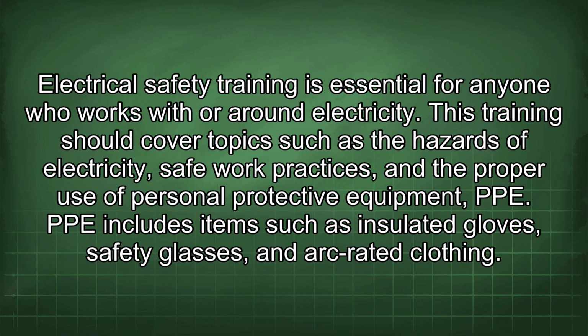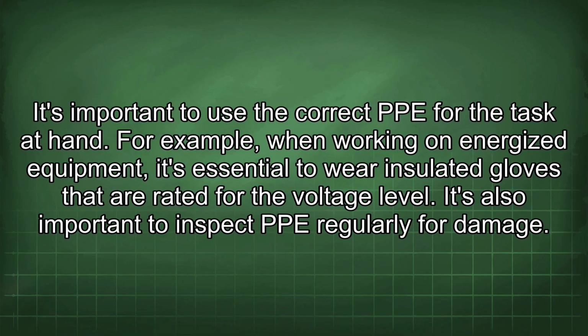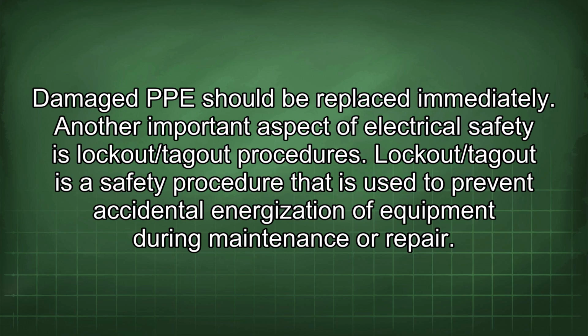This training should cover topics such as the hazards of electricity, safe work practices, and the proper use of personal protective equipment, PPE. PPE includes items such as insulated gloves, safety glasses, and arc-rated clothing. It's important to use the correct PPE for the task at hand. For example, when working on energized equipment, it's essential to wear insulated gloves that are rated for the voltage level. It's also important to inspect PPE regularly for damage. Damaged PPE should be replaced immediately.